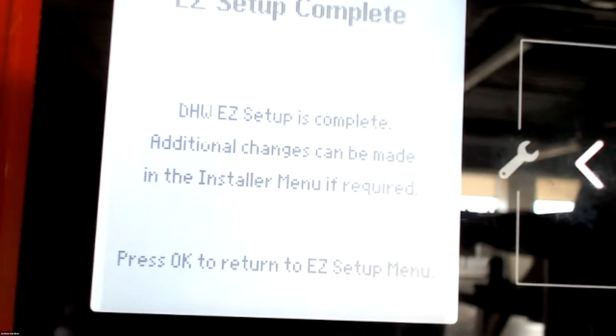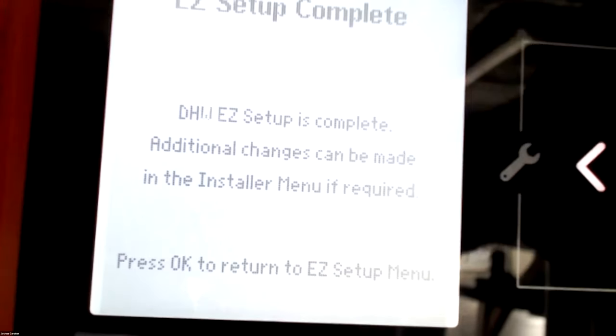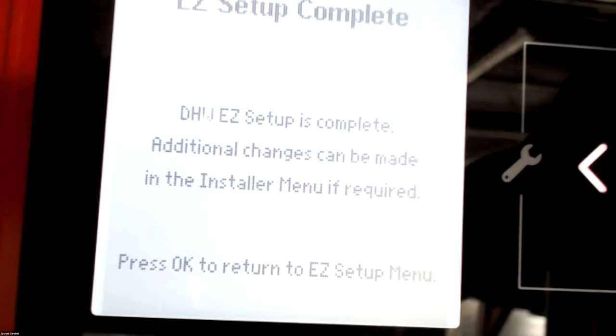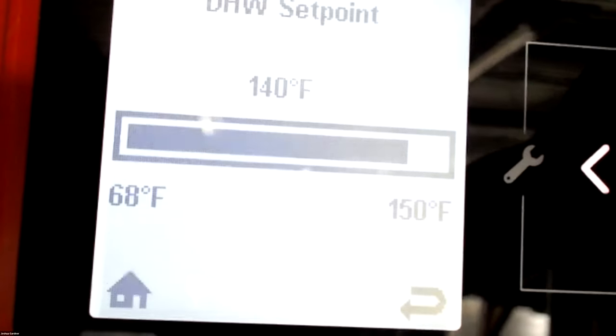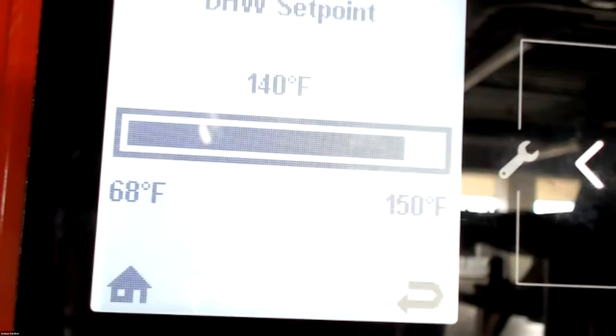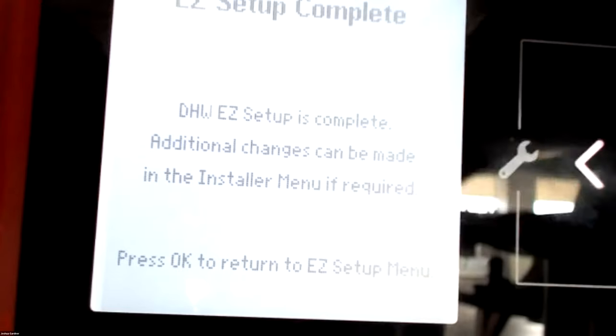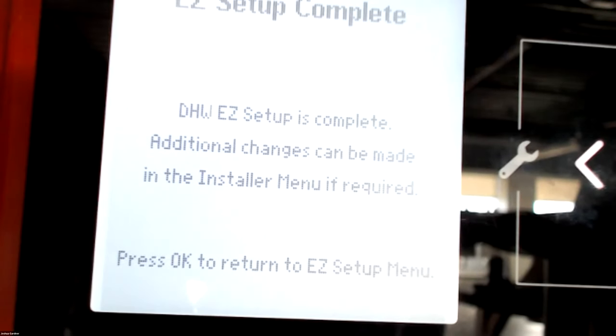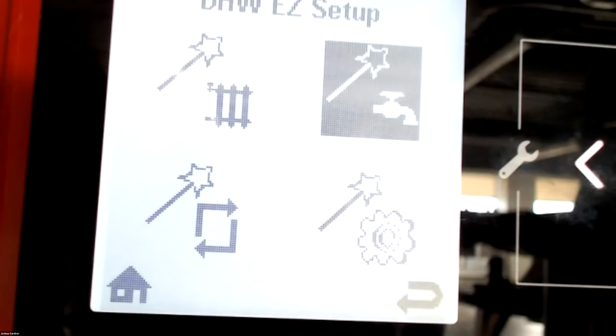All right. Now, what it didn't show is that, I think maybe we can do this if I pull the sensor. No, it won't let me. Except for combi. So if this wasn't a combi and this was a heat only, the first option in this domestic easy setup would have been thermostat or sensor. And that's where we pick thermostat or sensor, where we're running an aquastat or the tank sensor. So that's kind of the only difference.